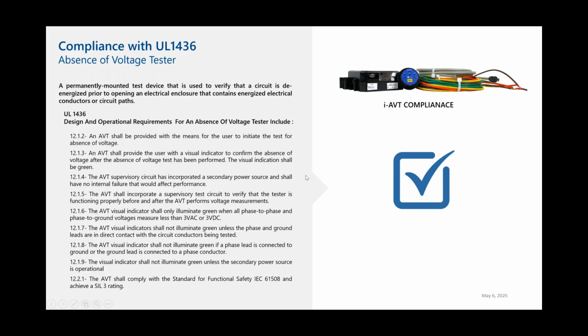A supervisory circuit has incorporated a secondary power source and shall have no internal failure that would impact performance. So the supervisory circuit is within the control box here, and the 2 leads AVTs basically have that supervisory circuit which confirms that we're still connected to the 3 phases and to ground. The AVT shall incorporate a supervisory test circuit to verify that the tester is functioning properly before and after the AVT performs voltage measurements. So again, that's also looping in through the supervisory circuit. And the visual indicators shall only illuminate green when all phase-to-phase and phase-to-ground voltages measure less than 3 volts AC or 3 volts DC.